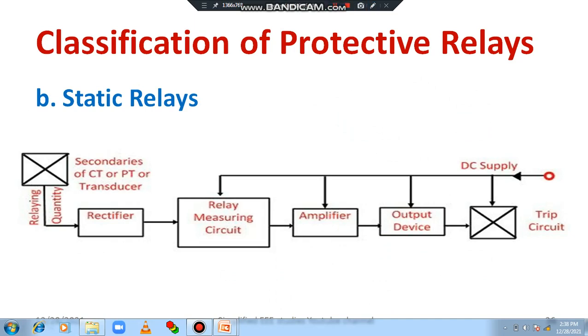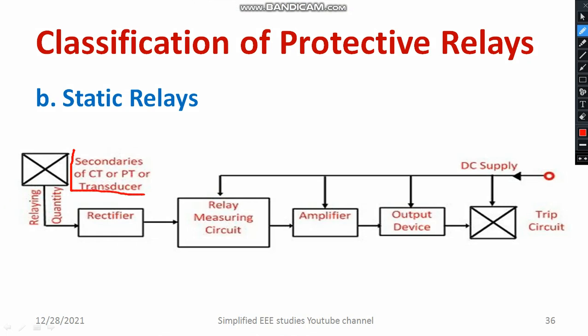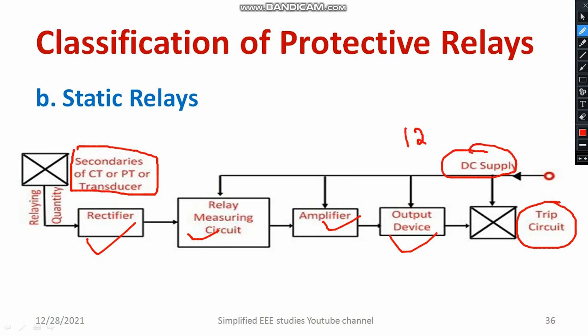Regarding the static relay: we need electronic components. We use a CT for measurement of current and PT for measurement of voltage. The relaying quantity — which is a varying quantity — is converted into a fixed quantity by using a rectifier, an electronic interface. The fixed signal is then fed to a relay measuring unit, which identifies the fixed quantity of signal and amplifies it. Afterwards it is connected to the output device and finally to the trip circuit. The relay measuring unit, amplifier, and output device all operate under DC supply only — a 12 or 24 volt DC supply is required.